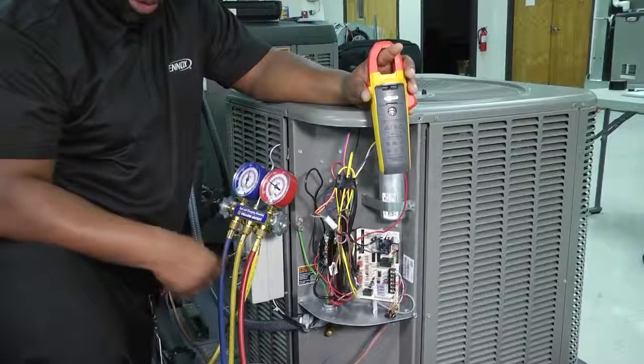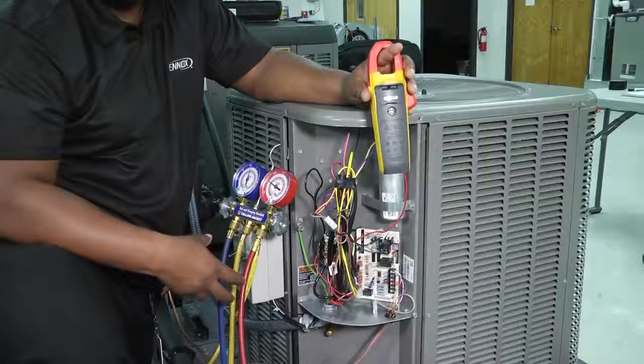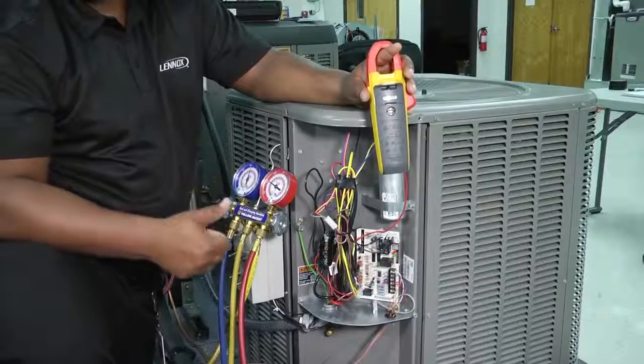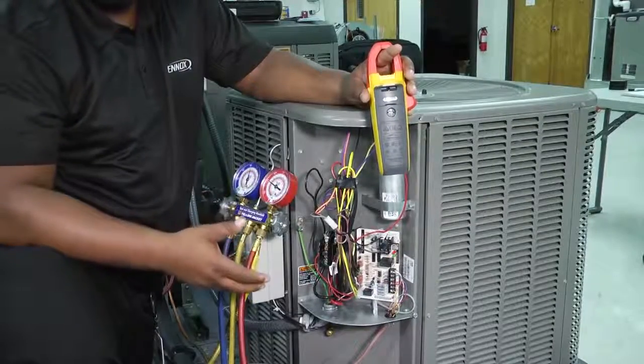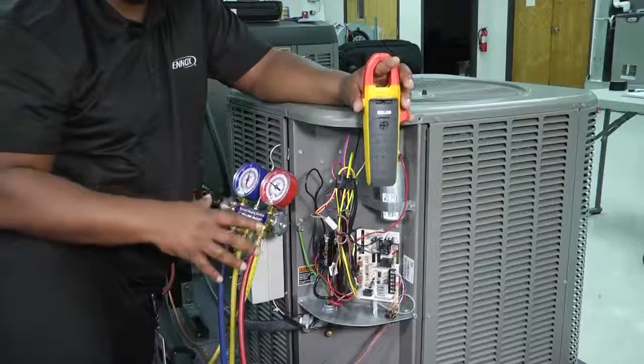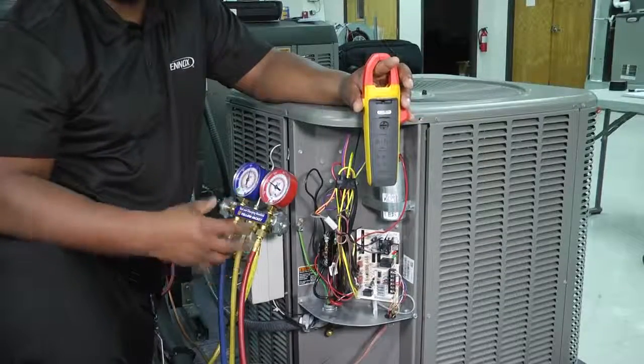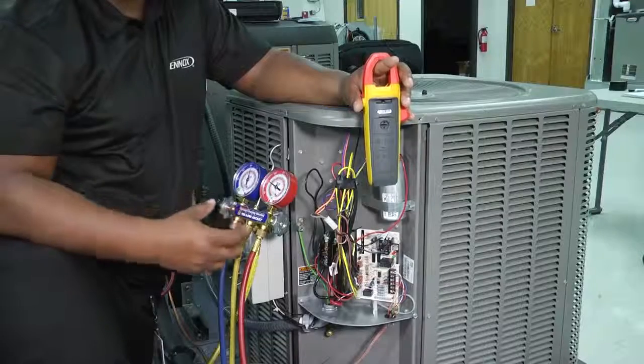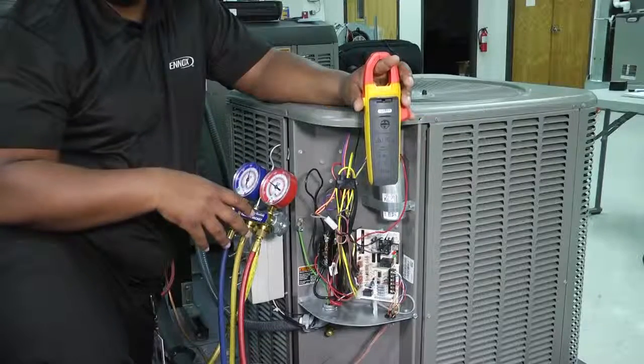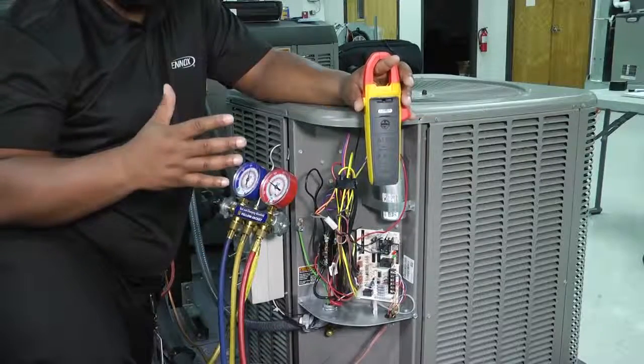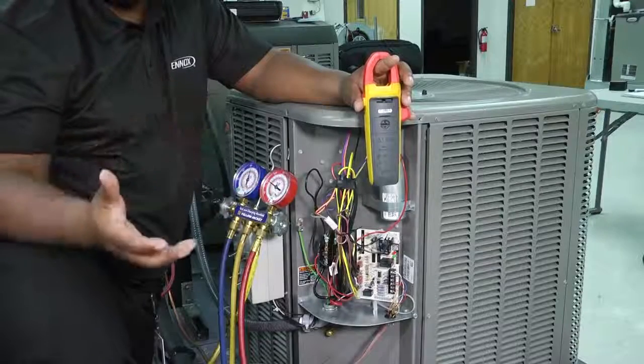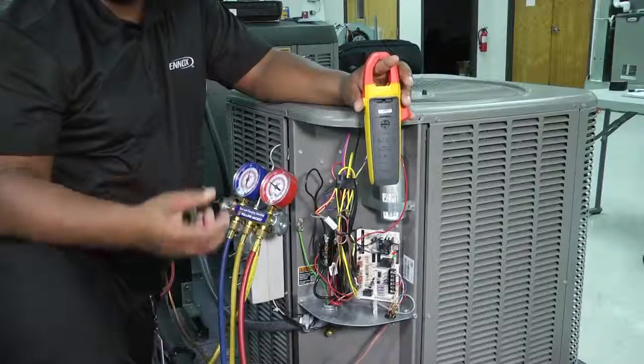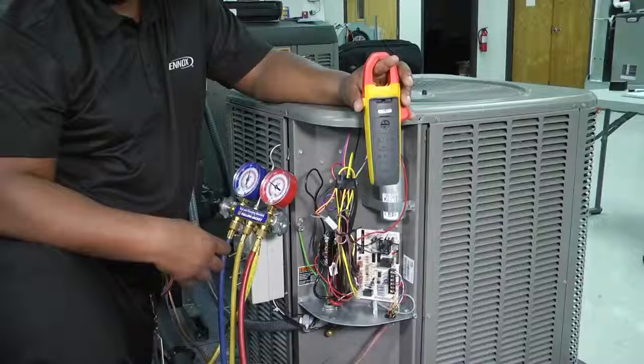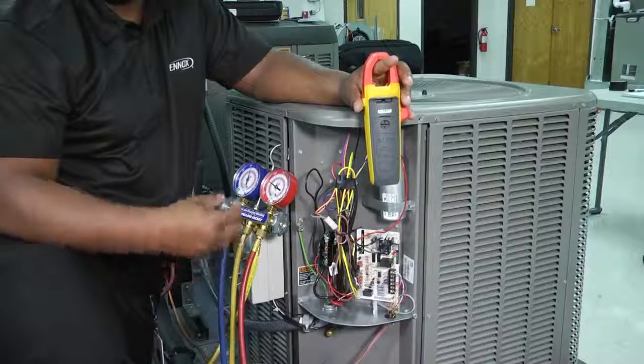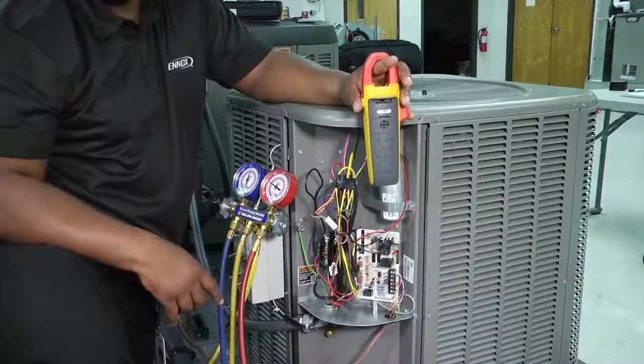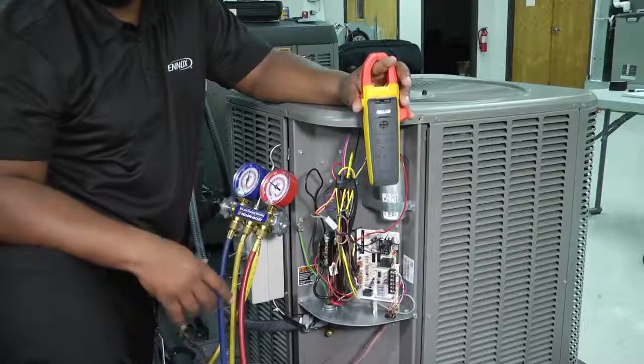So we have to make sure that we understand this particular process in our HVAC AC cleaning checks, or tune-ups rather, because it's vital to let us know what my refrigerant is actually doing within the system. So make sure we calculate our superheat and subcooling numbers accurately to make sure that our system is operating at optimal performance. Any adjustment or any error in those numbers may require that we add refrigerant or remove refrigerant, and it could be an indication that we have a possible bigger issue as it relates to refrigerant that we need to check.